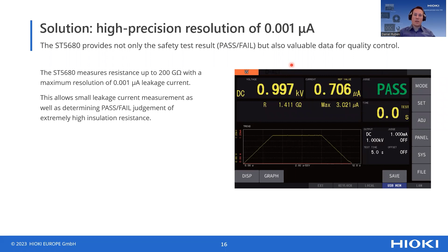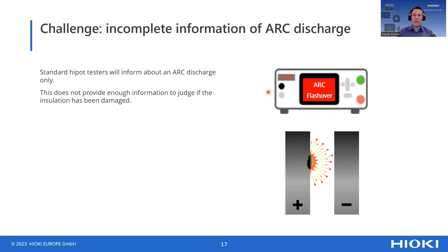Another challenge is to have arcs happening inside the battery pack, but only seeing "arc" shown on such a generic device. So what to do if you have only this kind of information? You will simply throw away the battery pack, could be a case, or you simply say, I have only seen one arc. Okay, let's keep it. The problem is that this kind of level of information is not giving you enough room for interpretation, and therefore it is best to also have a discharge waveform display.